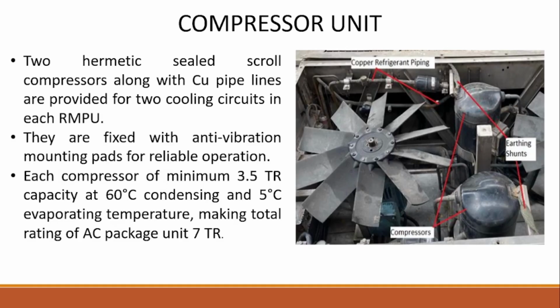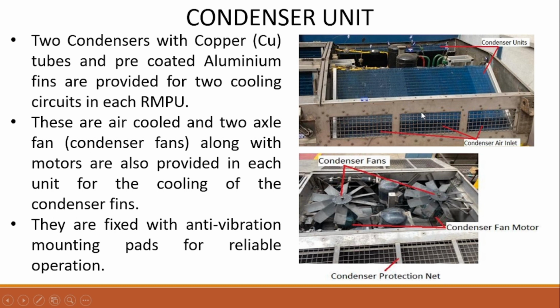Coming to the compressor unit, two hermetic sealed scroll compressors along with the CU pipelines are provided for the two cooling circuits in each RMPU. Each compressor has a minimum 3.5 TR capacity at 60 degrees Celsius condensing and 5 degrees Celsius evaporating temperature, making the total rating of the AC package unit 7 TR. So let's take a look at the condenser unit.